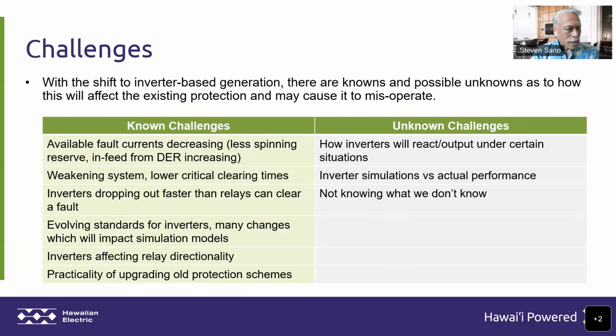So some known challenges: available fault currents are decreasing. Inverter-based generation does not have the same short circuit performance as rotating synchronous machines, and fault currents are decreasing. Our systems are getting weaker, meaning that our critical clearing times for transmission faults are getting lower. We have to clear faults faster. Inverters themselves can drop out faster than our relays can clear faults.